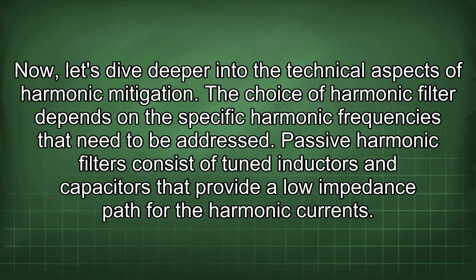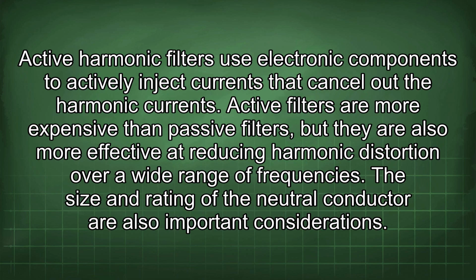Now let's dive deeper into the technical aspects of harmonic mitigation. The choice of harmonic filter depends on the specific harmonic frequencies that need to be addressed. Passive harmonic filters consist of tuned inductors and capacitors that provide a low impedance path for the harmonic currents. Active harmonic filters use electronic components to actively inject currents that cancel out the harmonic currents. Active filters are more expensive than passive filters, but they are also more effective at reducing harmonic distortion over a wide range of frequencies. The size and rating of the neutral conductor are also important considerations.